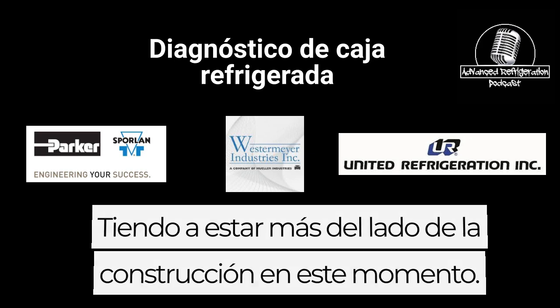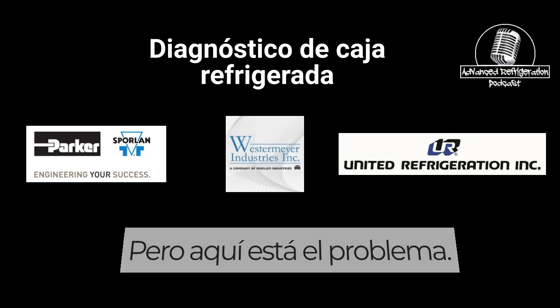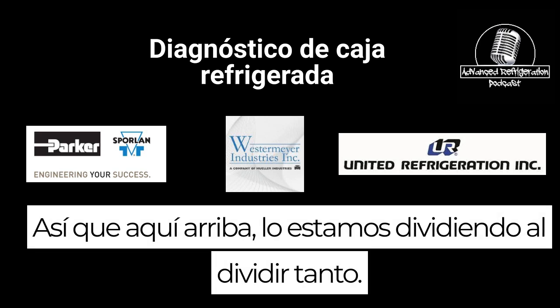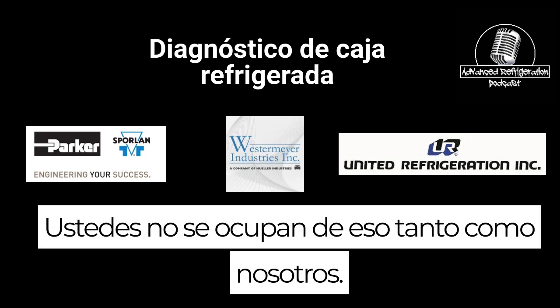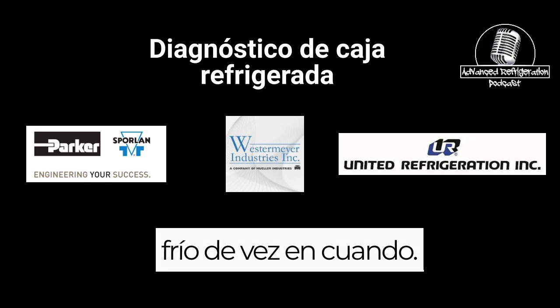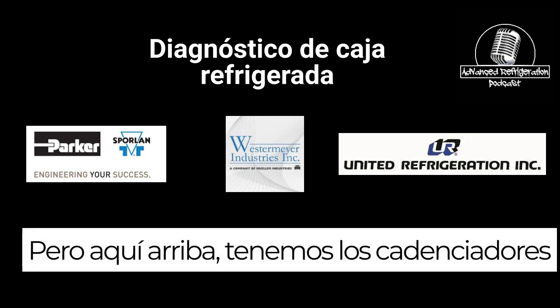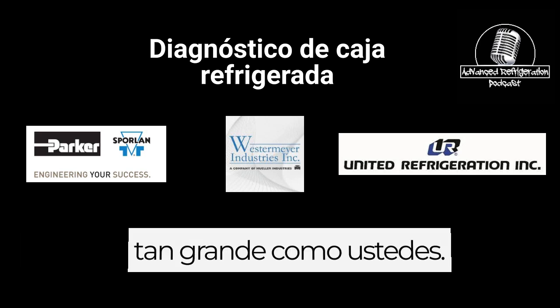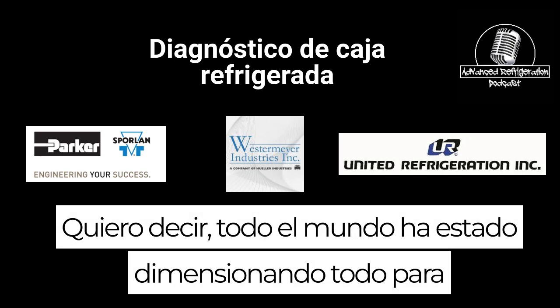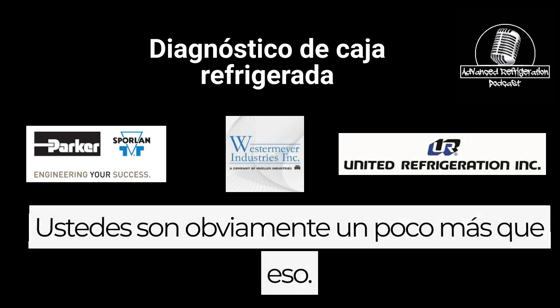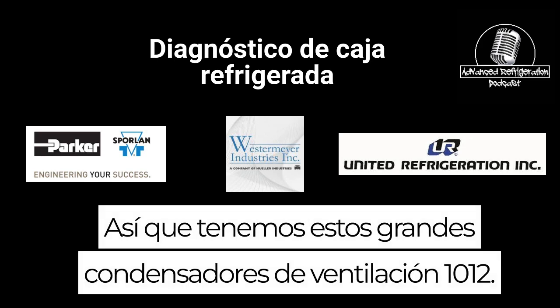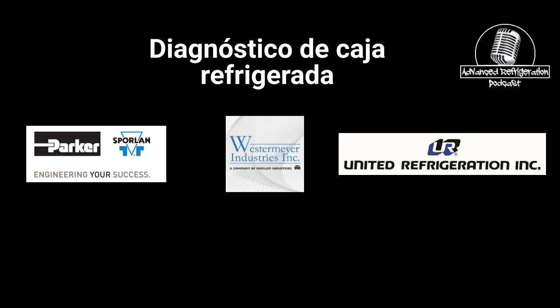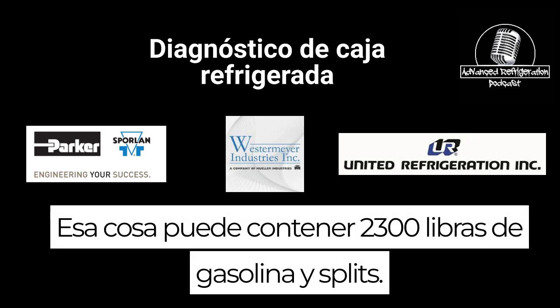I tend to be more on the construction side right now, but here's the problem. Up here, we're splitting so much. You guys don't deal with that as much as we do. You get down there, ambient's cold every once in a while, but up here we've got the condensers just as big as you guys. Everybody's been sizing everything for 110 up here for a while. You guys are obviously a little more than that, but we get these big 10, 12 fan condensers. That thing may hold 300 pounds of gas in splits.